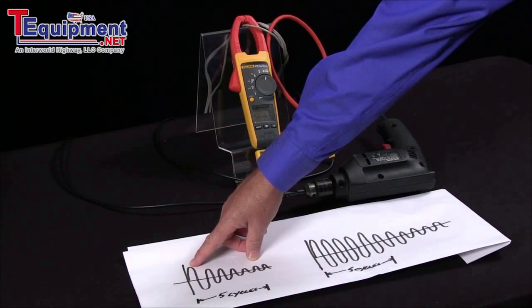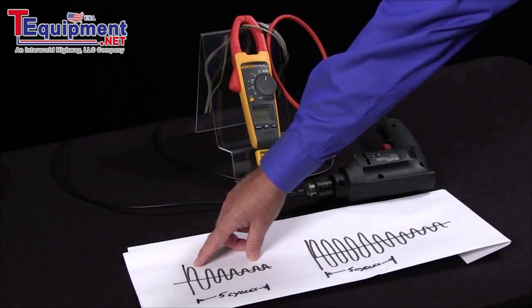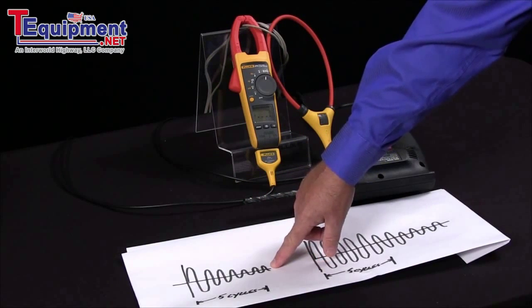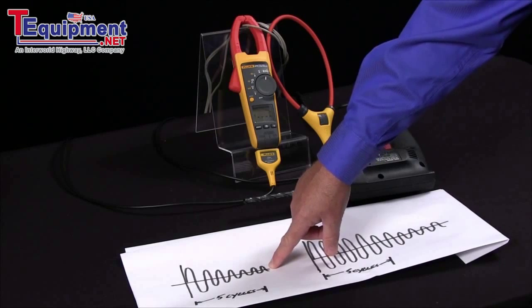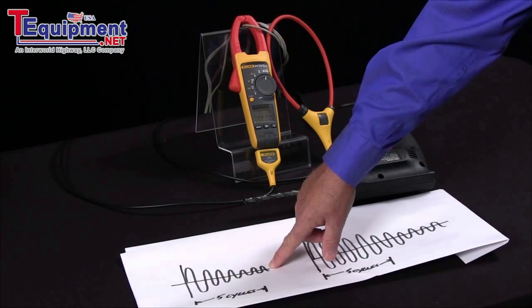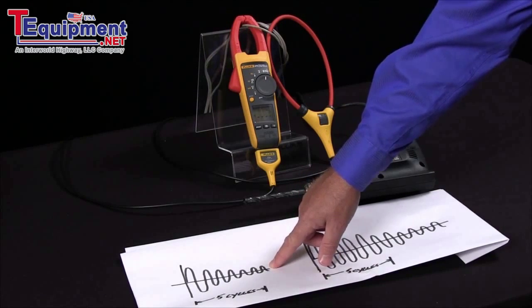the first peak that we see with the amps. We actually integrate it over 5 cycles. This gives you a truer measurement of your inrush current, which is more accurate than just doing a fast peak measurement.